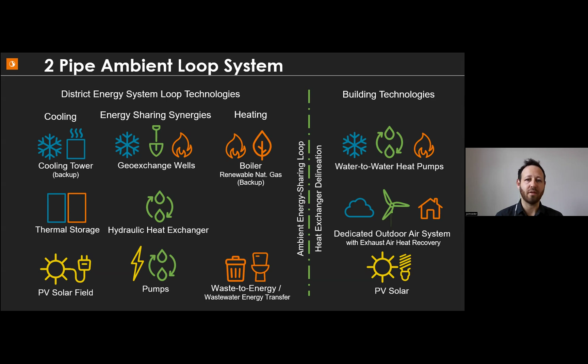The four-pipe system has other advantages and disadvantages. You're refining more of the energy at the energy centers, creating hot water and chilled water there, while still trying to keep those temperatures reasonable so you're not wasting a lot of energy in the distribution system. Maintaining those temperatures is great.